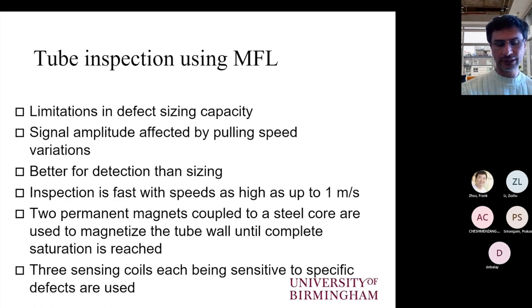One is the absolute coil, and the other two are the differential coils. The absolute coil is designed to detect general corrosion. The differential coils are designed to detect pitting corrosion and are more sensitive to smaller defects. Theoretically, we can also detect cracks, but MFL has restrictions in crack sensitivity, and the orientation of the crack and its location will affect its detectability.